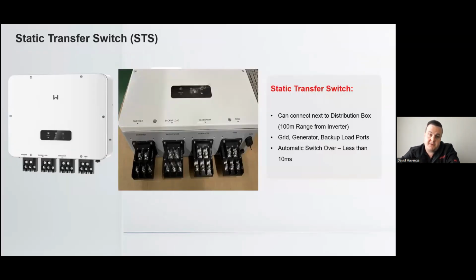So now looking at the smart transfer switch, the static transfer switch. The benefit of this static transfer switch, especially for installations, is this can be up to 100 meters away from your inverter. The smart transfer switch also has a 200 amp bypass current, so we can bypass current into loads. So your larger cables can be nearby your distribution board, from the STS to the distribution board, and then 100 meters to your inverter. Your inverter will be where your batteries are, maybe closer to the PV array. And then all you run is one singular AC cable from the inverter to the STS, along with a communication cable.